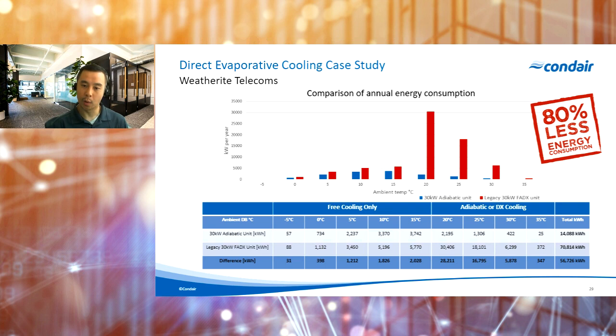If we look at that totaled throughout the year, going from a 30 kilowatt DX cooling system to a 30 kilowatt direct evaporative system results in about 80% less energy consumption for the same type of unit. So you can see that with this type of system, it really does make sense if you're in an area where you can take advantage of that free cooling.